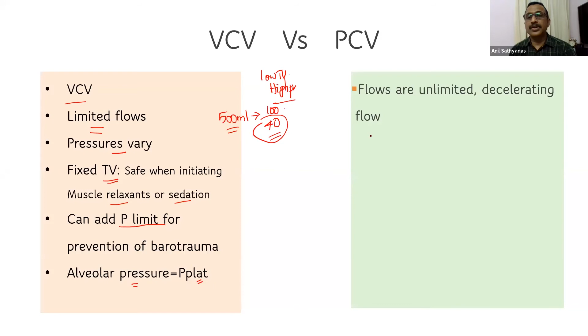We'll discuss this later. And remember, you have to measure the alveolar pressure by measuring the P plat. We'll discuss that later. You have to do a procedure called the inspiratory hold to get the P plat. We'll discuss that later. Whereas in pressure control mode of ventilation, the flow is usually described as unlimited, and it has a decelerating flow pattern.